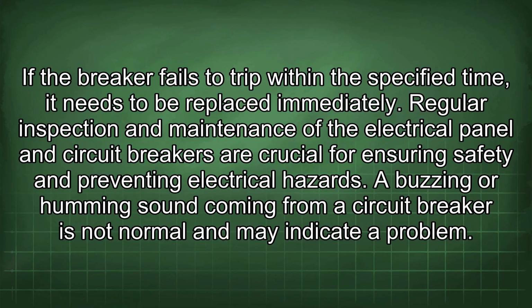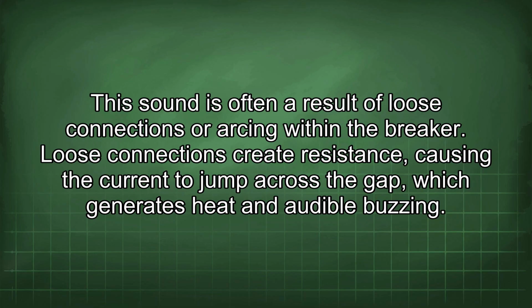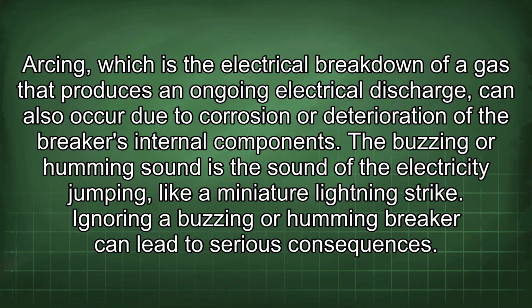A buzzing or humming sound coming from a circuit breaker is not normal and may indicate a problem. This sound is often a result of loose connections or arcing within the breaker. Loose connections create resistance, causing the current to jump across the gap, which generates heat and audible buzzing. Arcing, which is the electrical breakdown of a gas that produces an ongoing electrical discharge, can also occur due to corrosion or deterioration of the breaker's internal components. The buzzing or humming sound is the sound of the electricity jumping, like a miniature lightning strike.